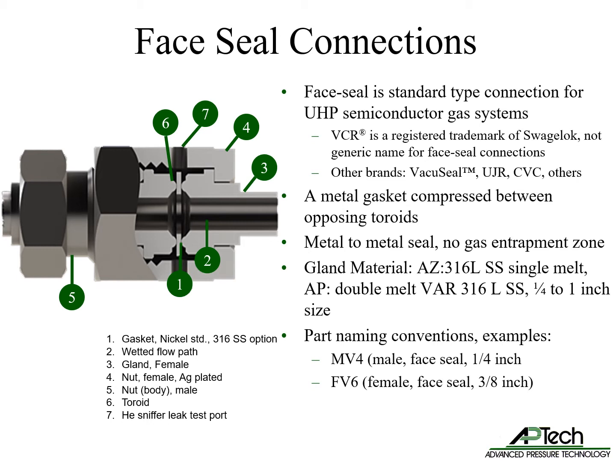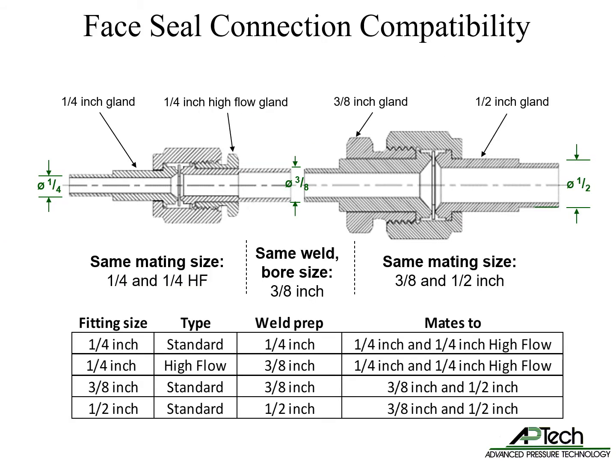When ordering, the part naming convention — for example, MV4 or FV6 — refers to male 1/4 inch or female 3/8 inch face seal, respectively. Some face seal connection sizes use the same nuts and sealing dimensions, enabling smaller or larger bore sizes to be connected using the same mating nuts, gaskets, and bodies. For example, 1/4 inch and 1/4 inch high flow glands and nuts mate, and 3/8 inch and 1/2 inch glands mate. A 1/4 inch connection size can be either 1/4 inch or 3/8 inch weld prep.